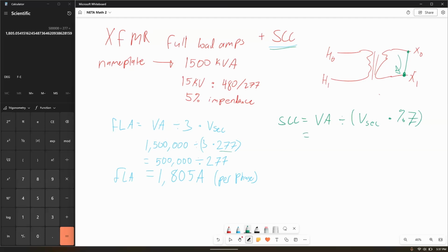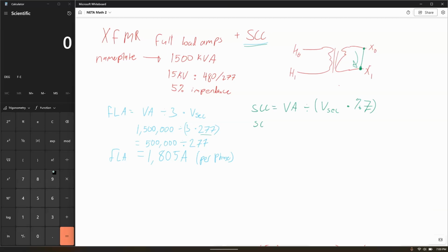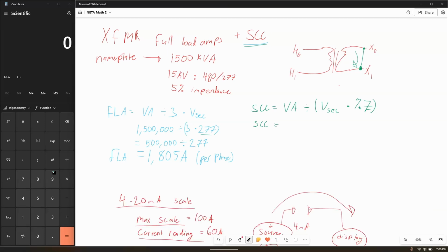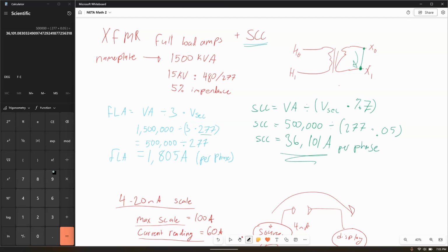So let's go ahead and plug and chug this real quick, just to run through it. Just as we did before, our short circuit current in this case is our single phase VA, because we're going to do this per phase. I want my short circuit current per phase. So it's 500,000 VA divided by my secondary voltage per phase times my percent impedance, which again is 5%. So we're going to go 0.05. 500,000 divided by, put this in parentheses, 277 times 0.05. I get a grand total of 36,101 amps per phase. This is substantially more than our full load amps.